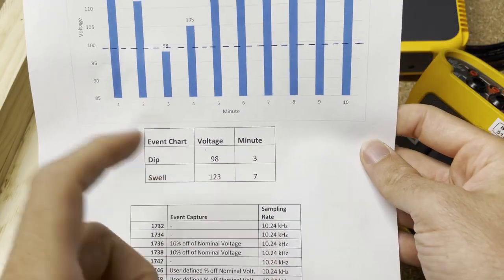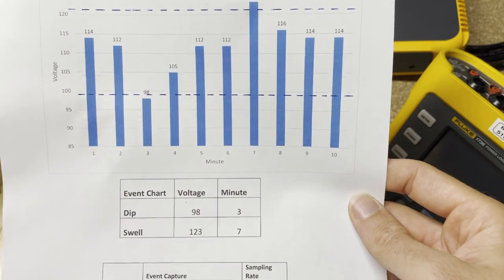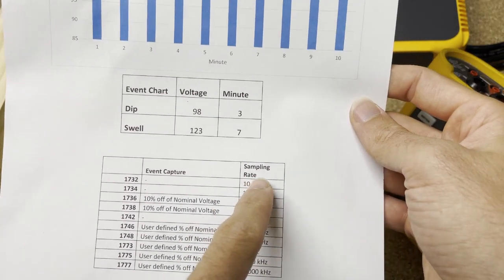Let me add one other thing that I think is a good analogy that I've heard before. When we think of sampling rate, that is how fast somebody blinks. If you close your eyes and somebody moves, and you close your eyes and somebody moves again, how fast you're blinking is your sample rate. But your demand or your trending interval is just how often you average the data. So we're not going to miss it based on the trending interval that we set, but we could miss it if we have something faster than our sampling rate.